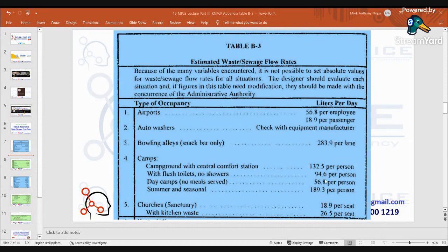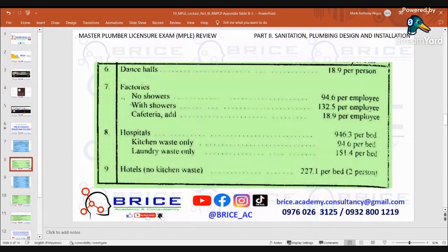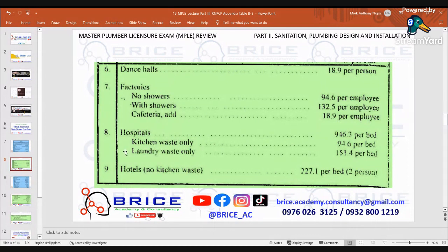With flush toilets, no showers: 94.6 liters per person. Day camps, no meals: 56.8 liters per person. Summer and seasonal: 189.3 liters per person. Number 5: Churches or sanctuary — 18.9 liters per seat; with kitchen waste: 26.5 liters per seat. Dance halls: 18.9 liters per person. Number 6: Factories — no showers: 94.6 liters per employee; with showers: 132.5 liters per employee.